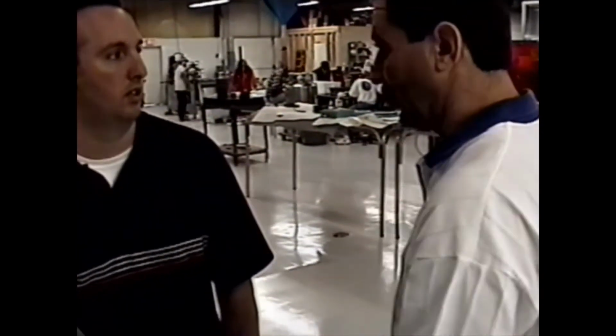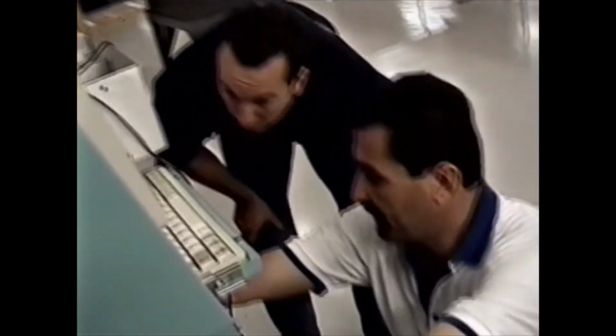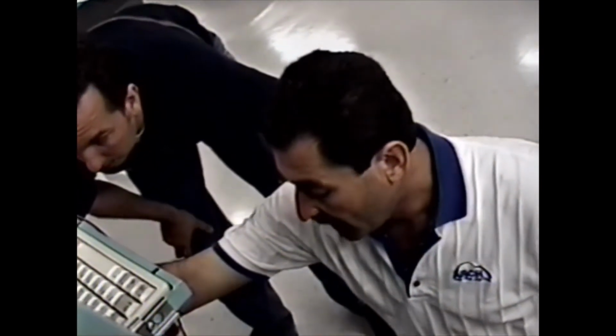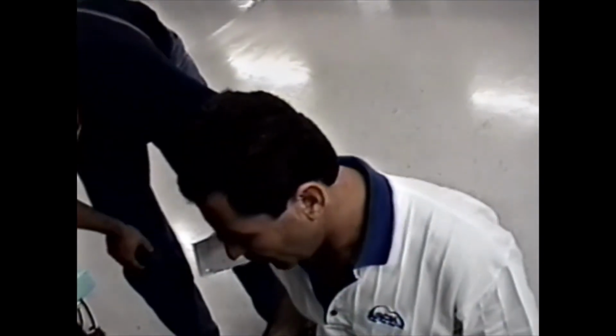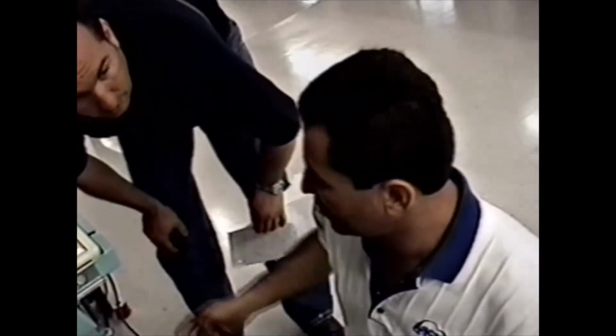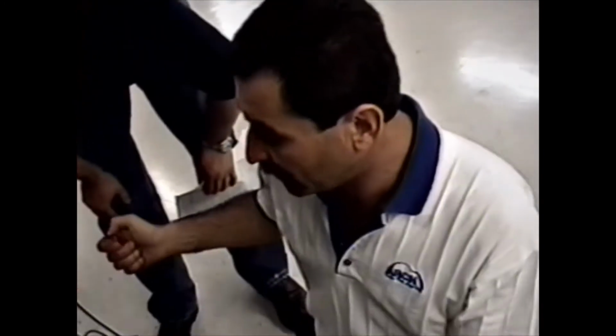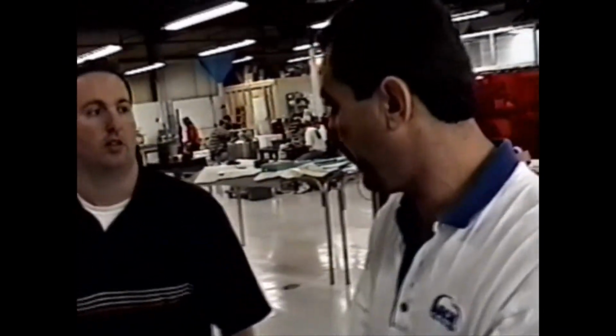I agree that you checked it over there, but this is part of it. Before you've done this one, you should have checked all the connections that they are leak tight. If you have 5, 6 of those, you're not doing 5, 6 of those by yourself. Somebody's going to come and put the manifold in for you, or you're going to put the manifold in yourself. You're assuming that what they did is 100% correct. That's wrong. You need to really protect the system.